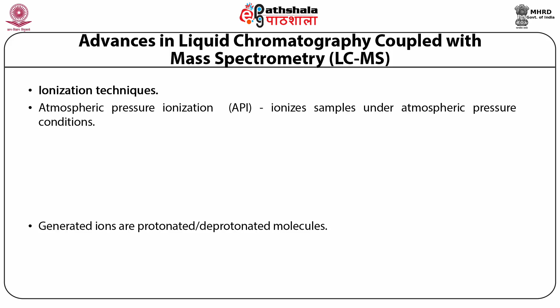At present, there are mainly two types of API interfaces. First is electrospray ionization, also known as ESI, and second is atmospheric pressure chemical ionization, known as APCI. The widely used method is ESI, and it is best applied to ionic compounds which are characterized by high polarity. In this method, a sample solution is drawn to the tip of a capillary tube and a high voltage of approximately 3 to 5 kV is applied.